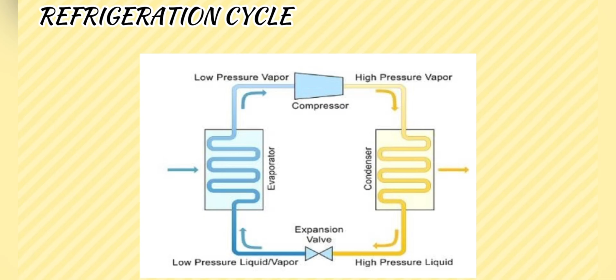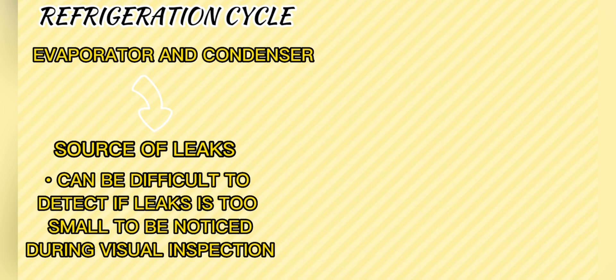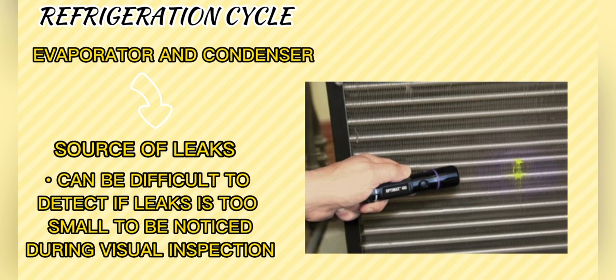We will look at 2 parts that have been the source of leaks in the refrigeration cycle, which is the evaporator and the condenser. Leaks can be difficult to detect immediately in both parts, as the leaks could be too small to be noticed during a visual inspection. Thus, the most suitable NDT that can be applied to both parts is eddy current testing. This type of testing uses a magnetic field to visualize flaws and defects in conductive material such as iron and copper. Eddy current testing can also detect issues that are invisible to the naked eye.